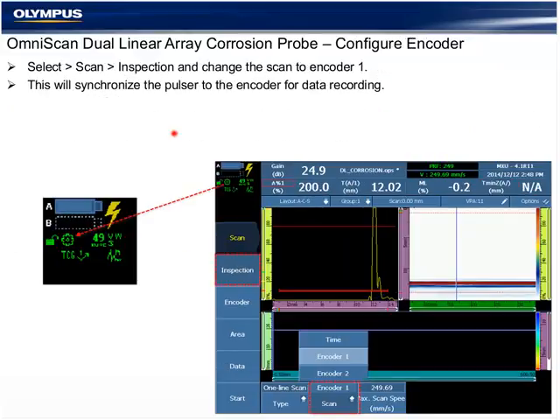The default configuration for the setup files is a scrolling time-based C-scan. That means that you see the C-scan building continuously, and it's not encoded, so it's not relative to the probe position at any time. It's just a visual indicator for the operator using color for thickness. If there's an encoder hooked up to the probe, or the probe is hooked up to a one- or two-axis scanner, and the hardware comes with scanner ports typical of Olympus scanners and ports for the mini wheel encoder, this will synchronize the pulser and the C-scan to the mechanical movement of the probe on the scan axis.